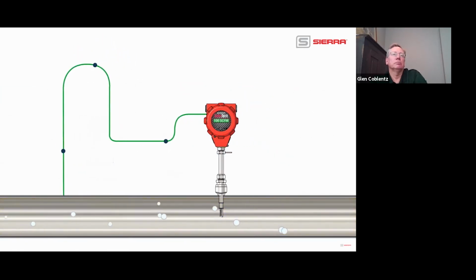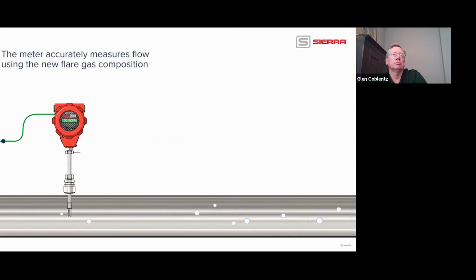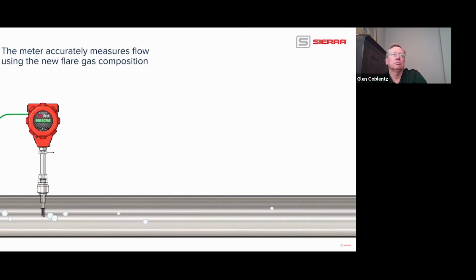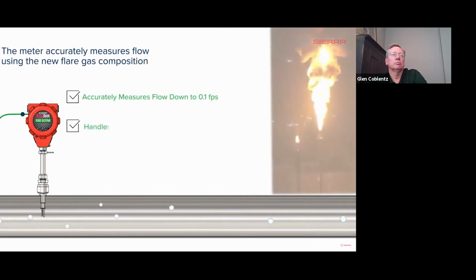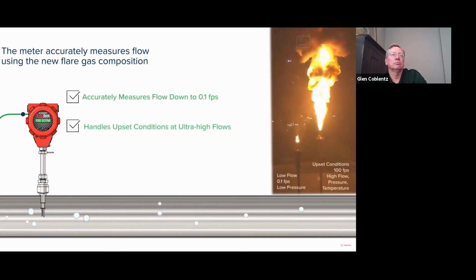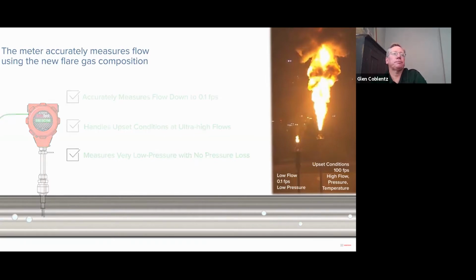The meter now accurately measures the new flare gas composition and measures flow down to 0.1 feet per second and maintains accuracy even with changing gas composition in real time. It handles upset conditions at ultra-high flows with wide 1,000 to 1 turndown and measures very low-pressure gas with variable temperatures with no pressure loss.